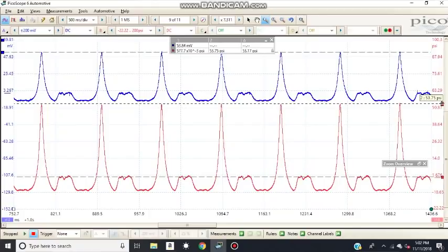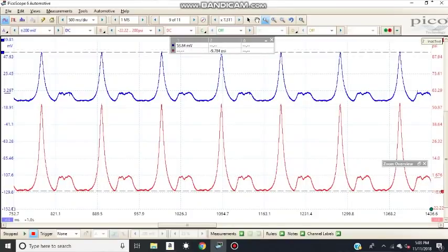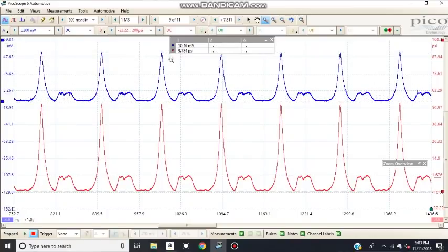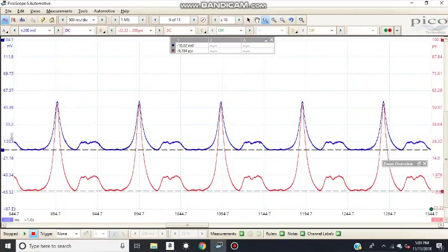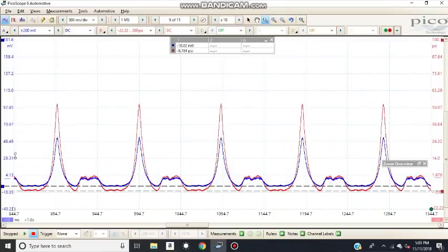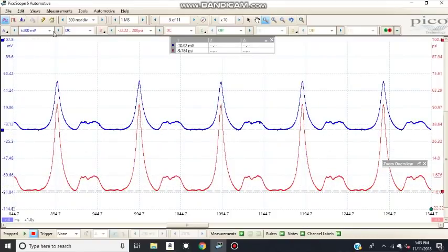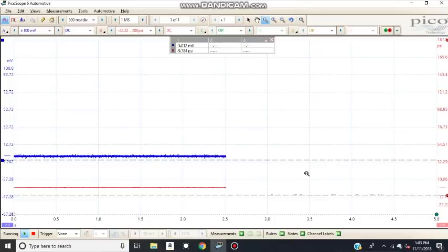So pretty close. Let's measure the negative pressure all the way down. We are at minus 9.7, and on the FLUKE 10.4. A little bit off, but close enough. The 9.7 is dead on. Now, as you can see here, I need to change my scale because I'm on a voltage. But we can see that they pretty much mimic each other. So let's change my scale on the FLUKE to 100 millivolts, and hopefully that will give us a better range on both signals.